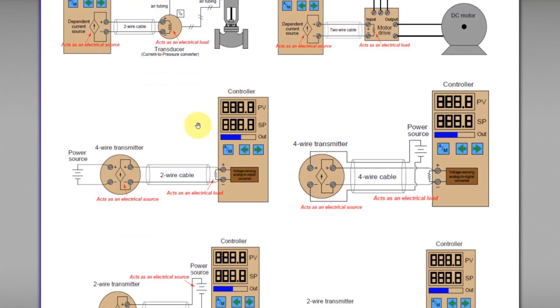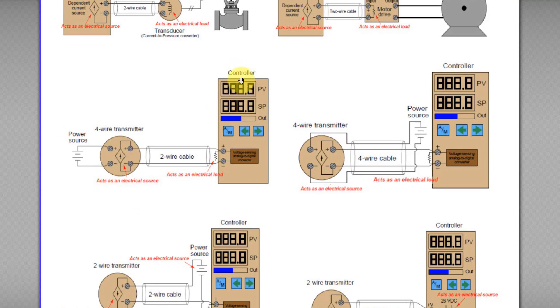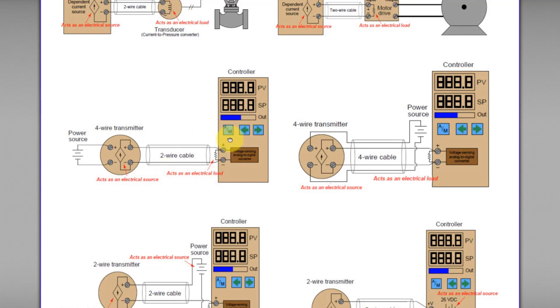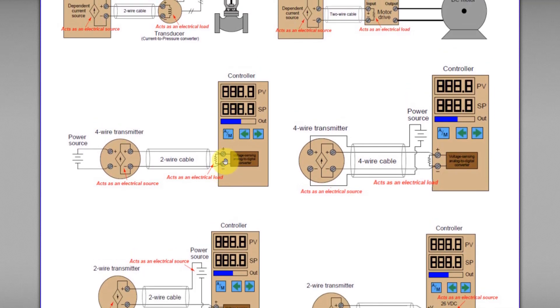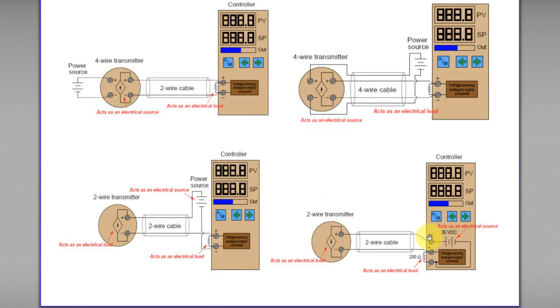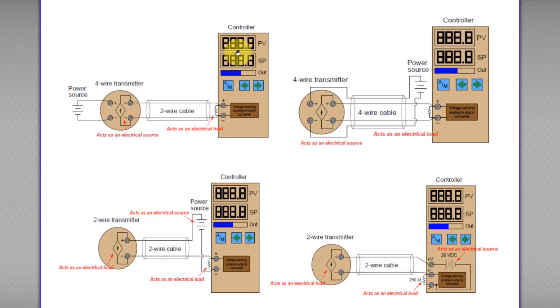How about this circuit? Now, the controller does not provide any power source to power the whole loop. Instead, the controller acts as an electrical load. How do we know? It's very simple. You can see there is a positive and negative terminal here, instead of a positive V terminal. If you see the positive V terminal with a wire connected to it, it means this controller will provide the power source, because the positive V — positive voltage — is internally connected to its internal power source. So this controller acts as an electrical load.